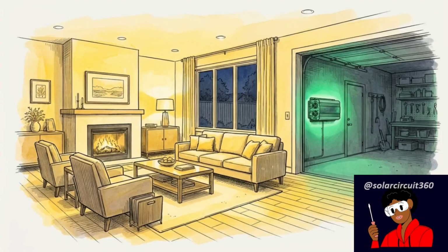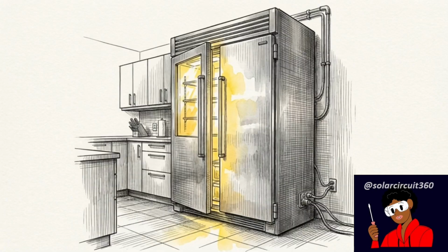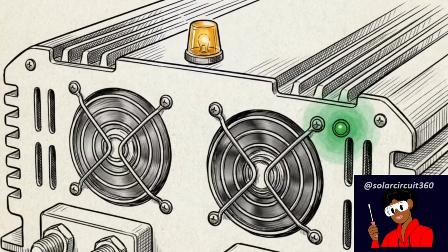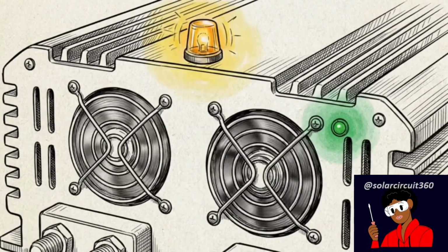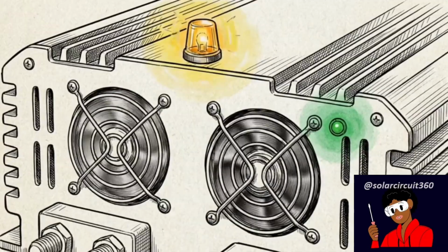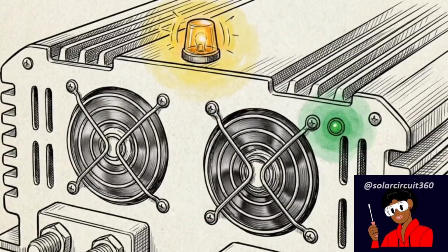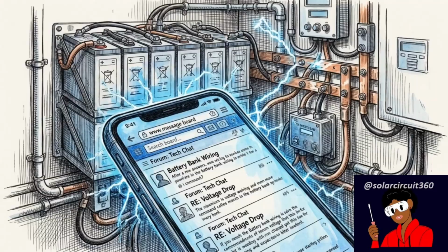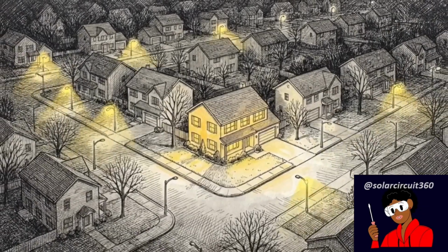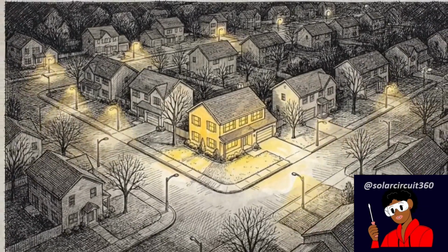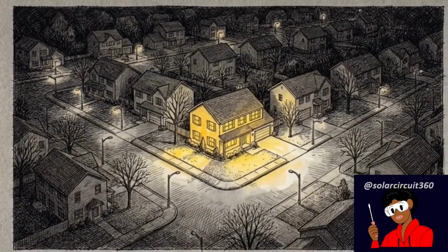Let's revisit the blackout scenario, this time with a system properly configured with a dual controller hierarchy. When the heavy load kicks on and the battery depletes, the inverter preemptively sheds power and triggers its alarms, managing the event exactly as designed without blacking out the DC system. Copying settings from an online forum ignores the specific mathematical coordination required for the exact hardware in the room. When the grid fails, system reliability depends on the coordination between the inverter's software logic and the battery's specific chemistry.